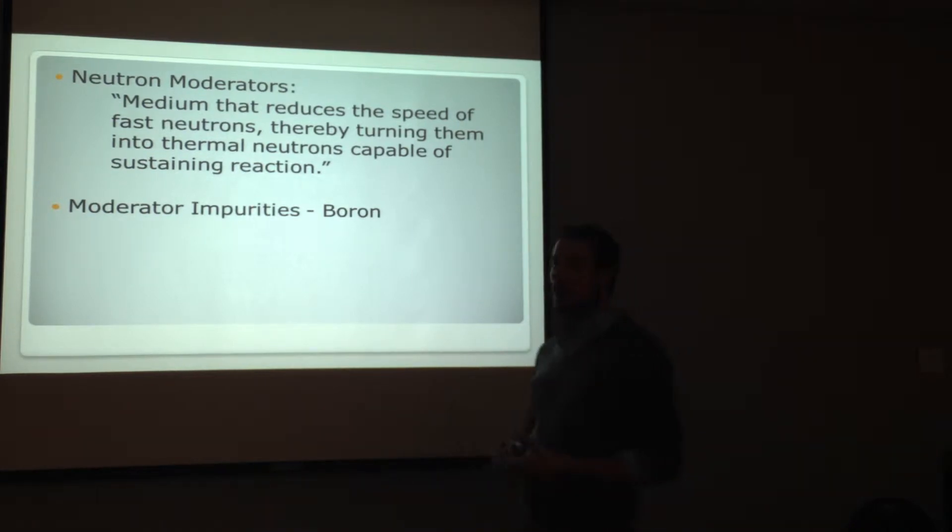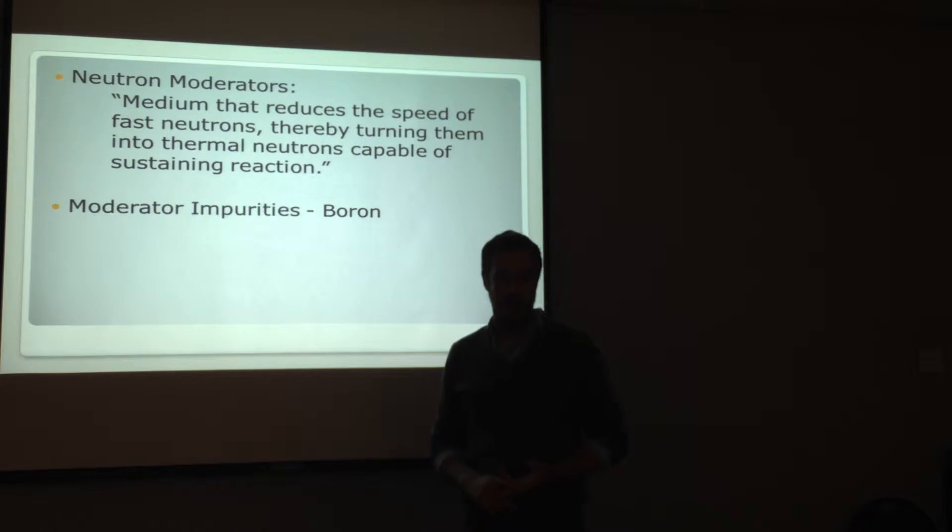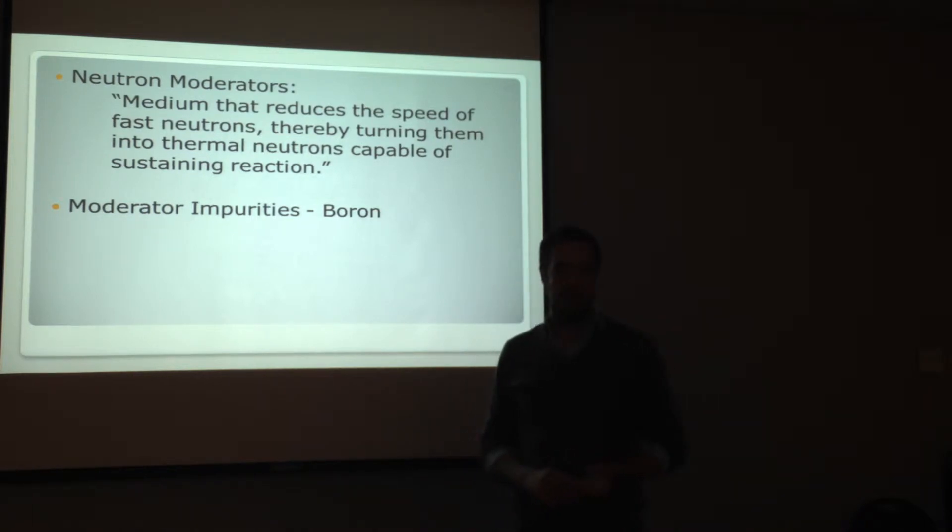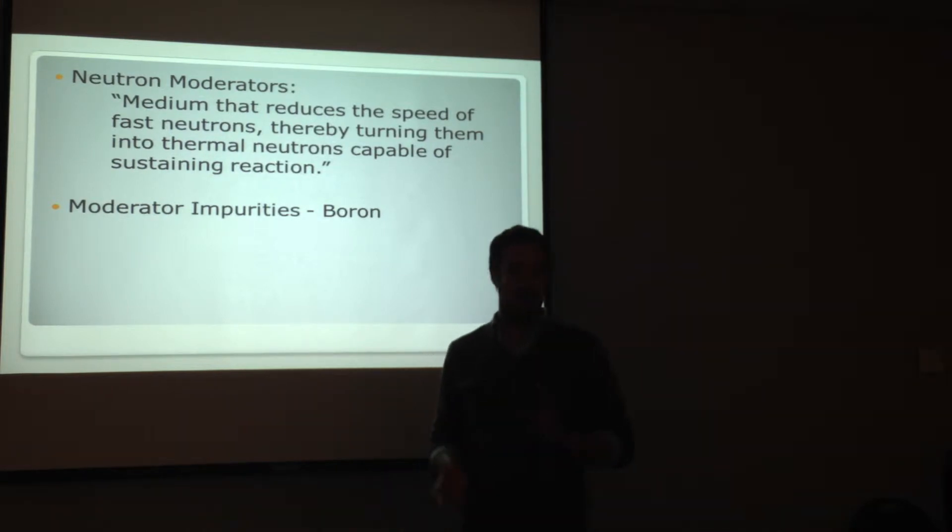Generally, a good moderator is considered a moderator that doesn't have impurities. But in the case of reactor control, we want some impurities in that moderator because the impurities give us a way to control the rate of reactivity, control flux, tilt, and power distribution. And one of the impurities that is commonly used, especially in pressurized water reactors, is boron. Boron is introduced to the system and controlled and diluted and used to control reactivity as the core goes through its life.